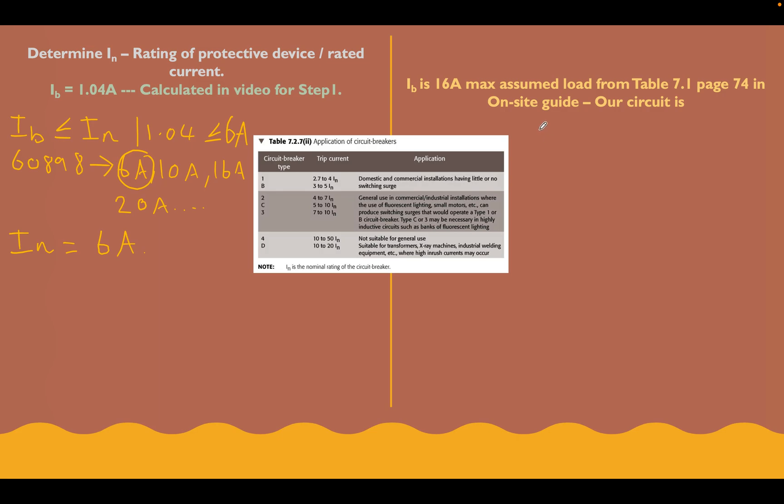On this side, exactly the same thing again. We know that our design current here is 16 amps. We got that from the assumed load table that we looked at in step 1. And we know the same again - our rating of our protective device we choose has got to be greater or equal to this number. On this side, we're using something which is similar but slightly different. We're using an RCBO, which is 61009, and these are made in preset values as well.